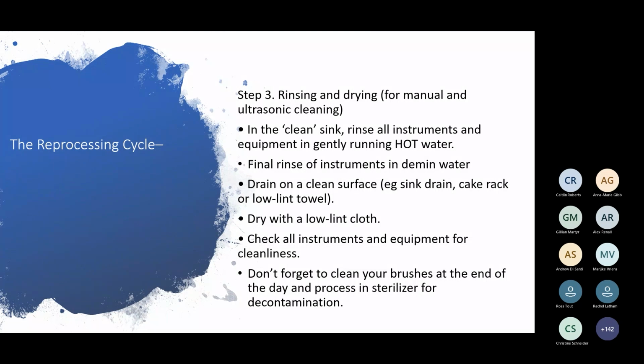So once they're cleaned, in the clean sink, rinse all your instruments and equipment in gently running hot water. So this is when you can use hot water, okay? The final rinse of instruments then needs to be in demineralized water. Now, you may not be using demineralized water at the moment, but you should be. The standards all clearly say that you need to be using demineralized water for the final rinse of instruments. And the new standard that is being developed at this point in time has clear guidelines that you probably have to use demineralized water through the whole process, but definitely the final rinse of your instruments is in demineralized water.